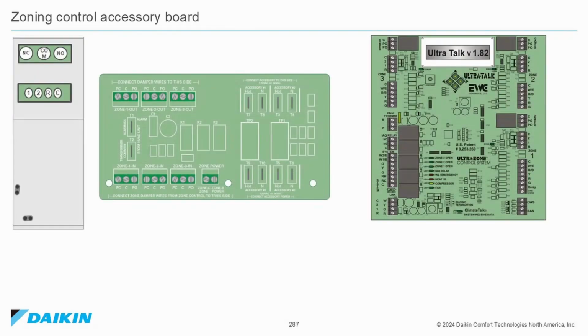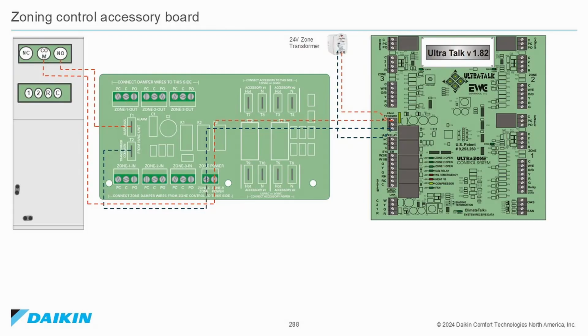Zoning Control Accessory Board. From the Indoor Unit Control Board, wire the common terminal to the Zone Controller Power on the Zoning Control Accessory Board. Wire the normally open to T1 on the Zone Control Accessory Board. The wires from the Zone Power connection on the Zone Control Accessory Board should be routed to the P and C terminals for the 24-volt transformer on the EWC Zone Control Module. The 24-volt transformer should also be wired to terminals P and C of the 24-volt transformer terminal on the EWC board.